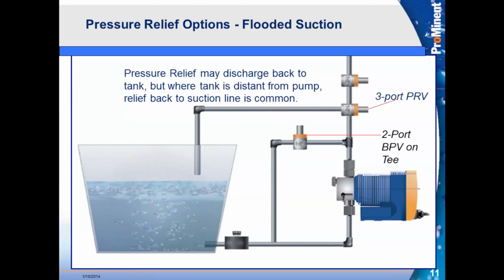Alternatively, the 3-port device, which is again below, or before, if you will, the back pressure valve, comes off and goes back into the supply tank in this case. We don't have it going back into the suction line, but into the supply tank. So either is acceptable. Quite often on our skids, you will see a second back pressure valve, a 2-port device, coming off of the T and going back to the suction line, just like you see here.